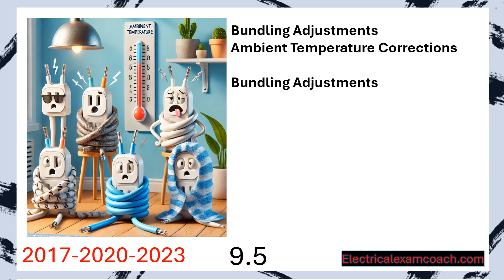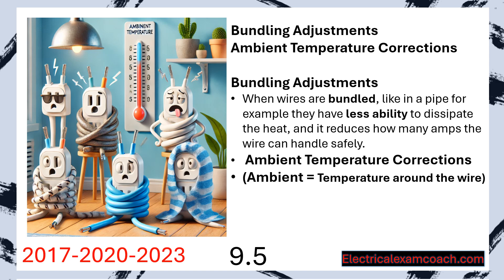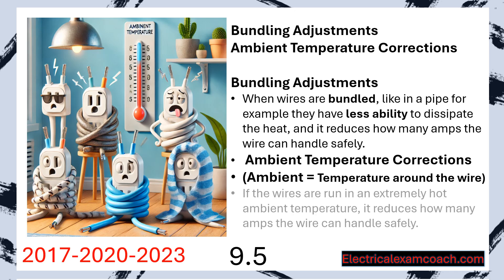Bundling adjustments work like this: when wires are bundled, like in a pipe for example, they have less ability to dissipate the heat and it reduces how many amps the wire can handle safely. Ambient temperature corrections are like this: if wires are run in an extremely hot ambient temperature, it reduces how many amps the wire can handle safely.